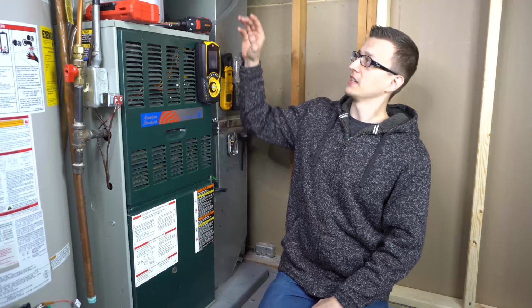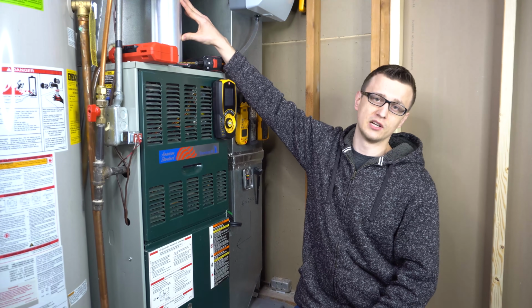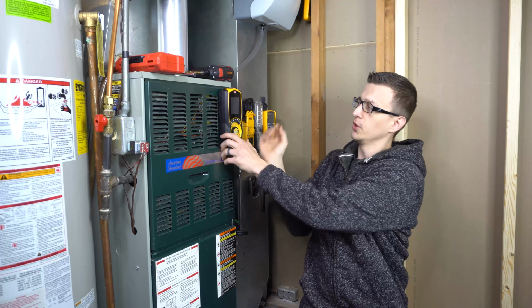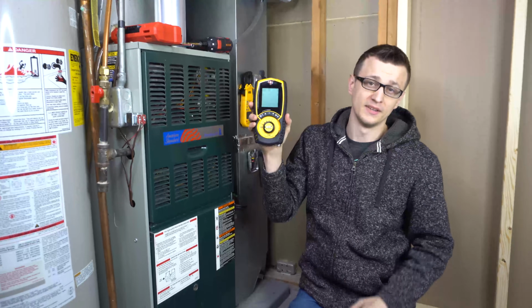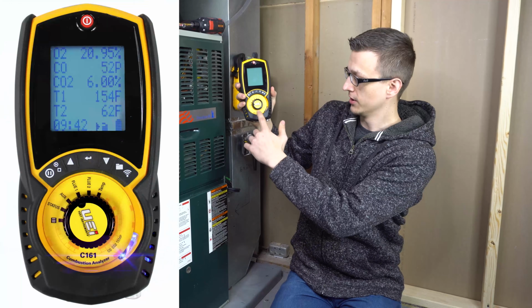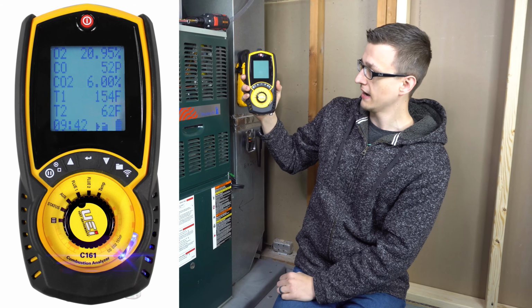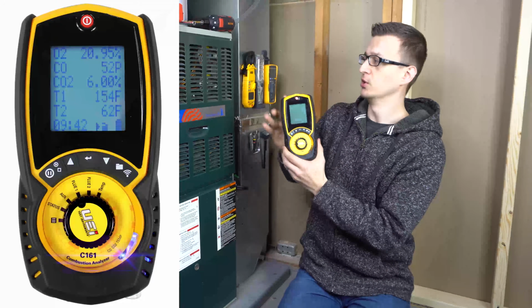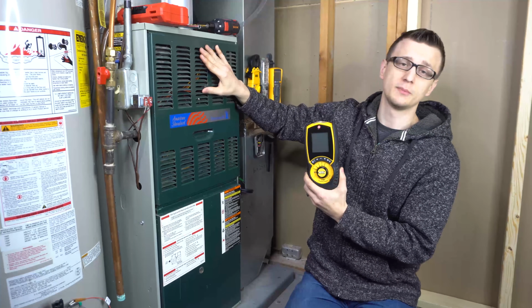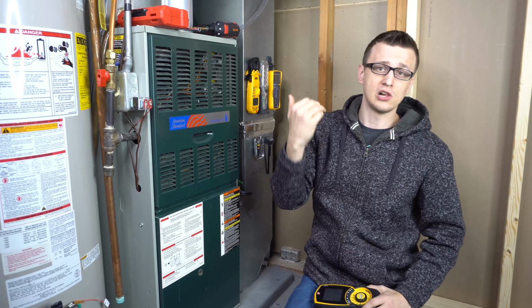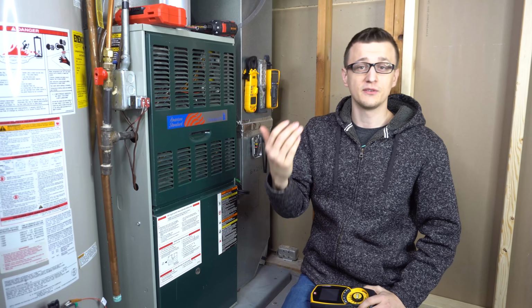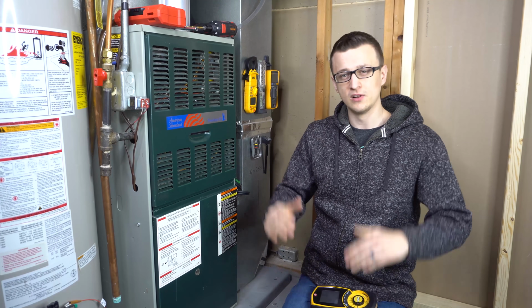In this video, I will be explaining how to check carbon monoxide levels in a furnace flue using a combustion analyzer. In my demonstrations, I'll be using the UEi C161 analyzer, and I'll be checking the flue levels of this furnace right here, which is a two-stage 80% furnace.